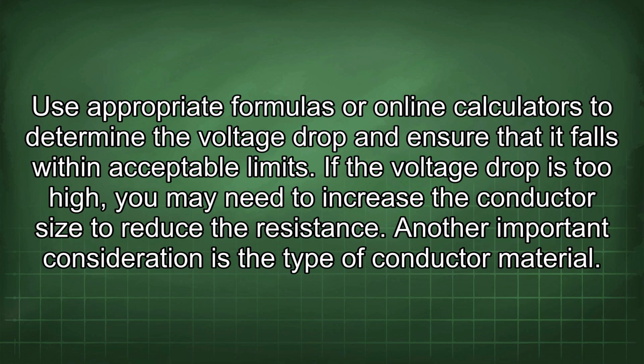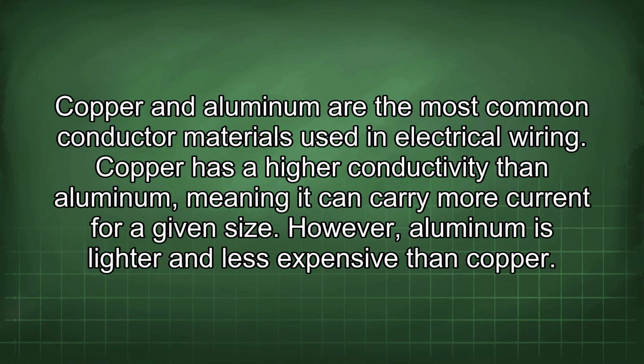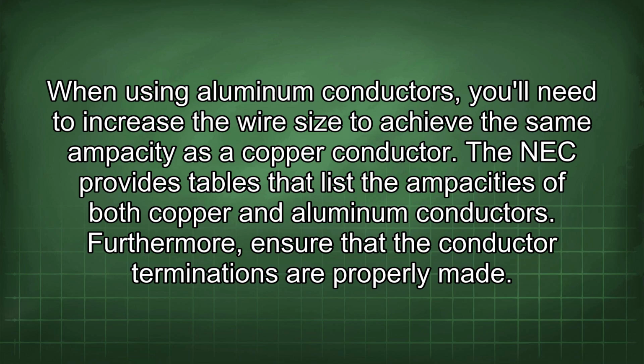Another important consideration is the type of conductor material. Copper and aluminum are the most common conductor materials used in electrical wiring. Copper has a higher conductivity than aluminum, meaning it can carry more current for a given size. However, aluminum is lighter and less expensive than copper. When using aluminum conductors, you'll need to increase the wire size to achieve the same ampacity as a copper conductor. The NEC provides tables that list the ampacities of both copper and aluminum conductors.